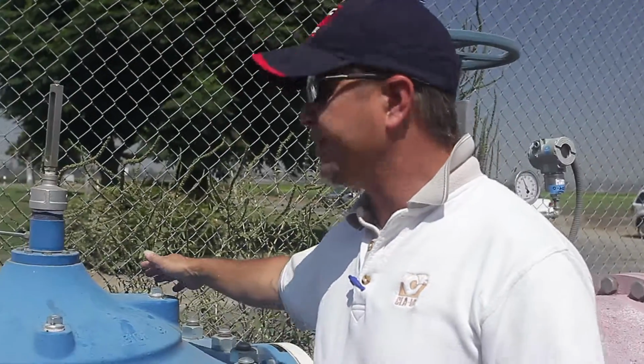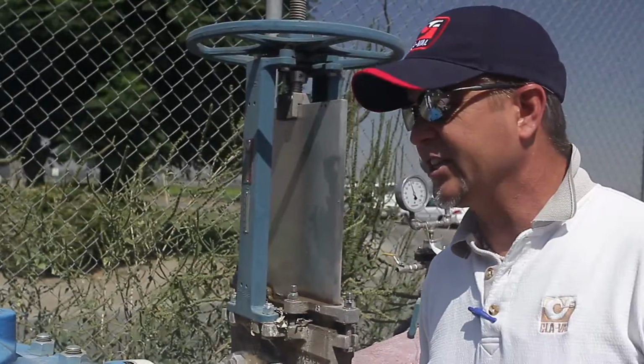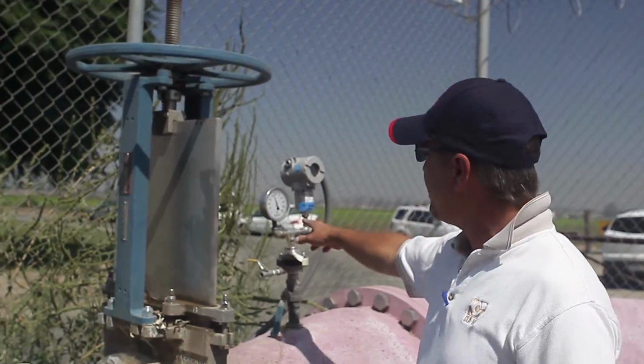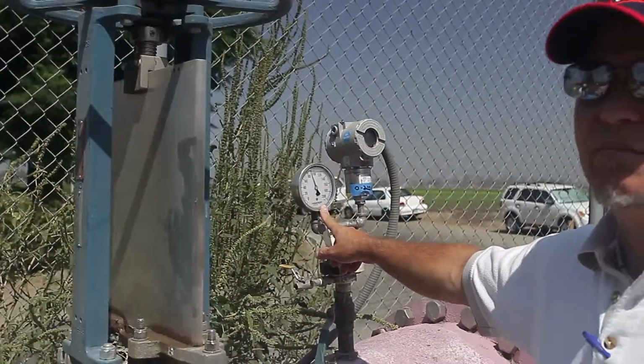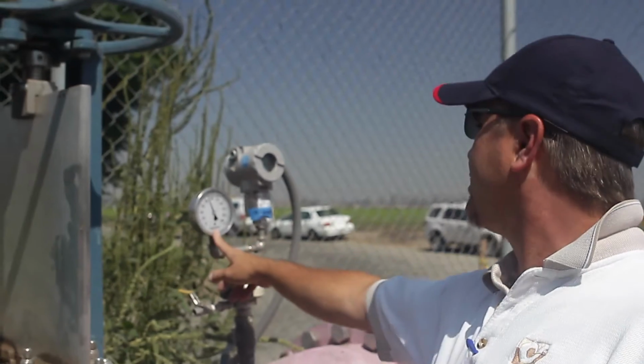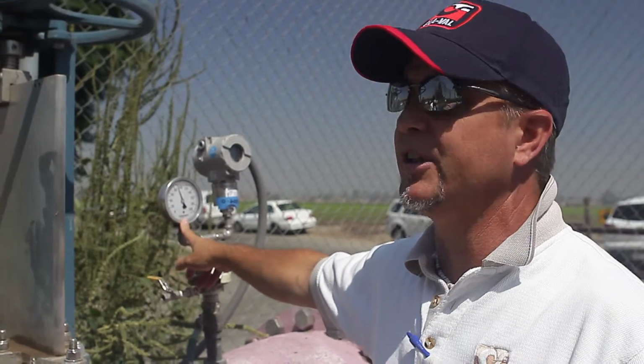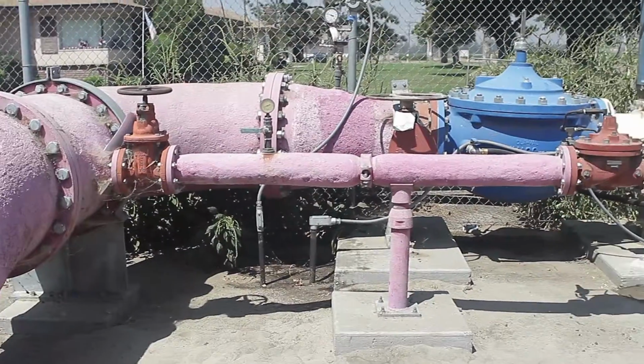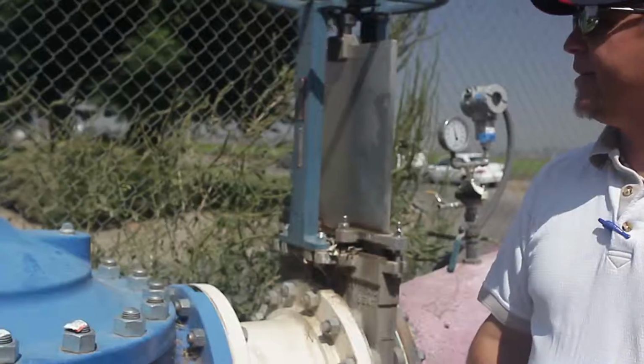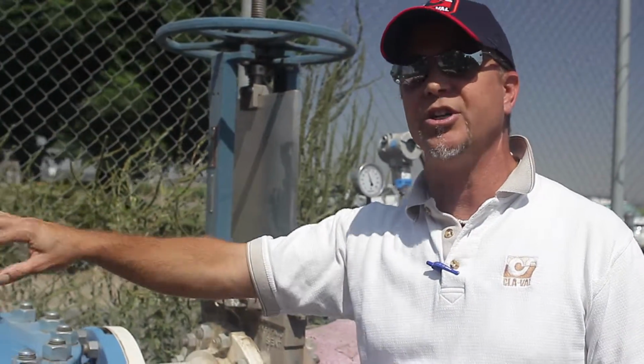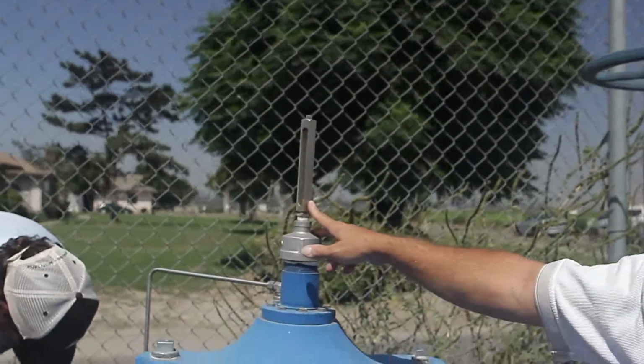All of the controls for this valve are on the other side. This is a pretty straightforward pressure reducing valve. It takes the high upstream pressure, which is about 90 pounds or so currently, and reduces it down to approximately 45 pounds. And that's its job. It doesn't know the flow, it doesn't care about the flow, it only reduces the high upstream down to a manageable low pressure. On top here we have a position indicator.